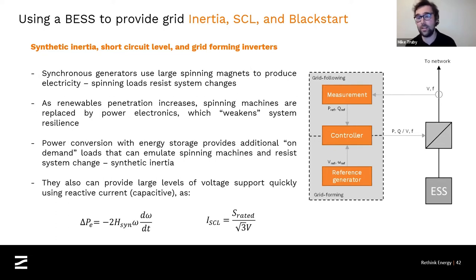The final thing that we can start to do as inverter technology improves is black start. Traditionally, BESS inverters, battery inverters, are what they call grid following. And actually, in response to one of the questions that I saw come up, the Capenhurst site is a grid following site, which means that you are measuring what is happening at the network and then responding to it. But the newest generation of inverters are now capable of what they call grid forming. So rather than measuring the system voltage and frequency, we're able to generate internal references. Essentially, rather than following the synchronicity of the system, we're able to set it. This means that for this generation of battery assets onwards, we will be able to deploy systems that can provide black start to the network without the need for black start generators. These batteries will be capable of doing black start.